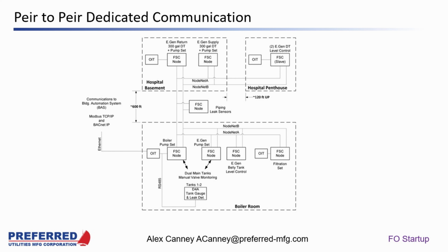Another big advantage we didn't necessarily anticipate is if you have an existing fuel system and you're trying to update the controls, it can be hard to decide: do we pull the old system down and be completely offline until the new system is hooked up? That can take a long time, especially in a hospital that's occupied. Or do we try to run an entire new set of wiring for all the new controls and accessories in parallel to the existing system? There may not be space for that, and it's extremely expensive.